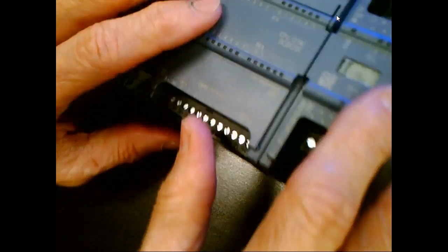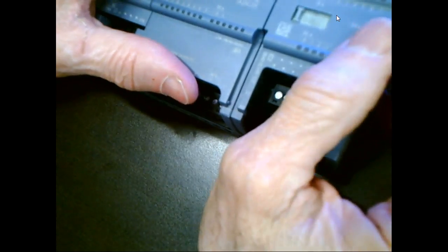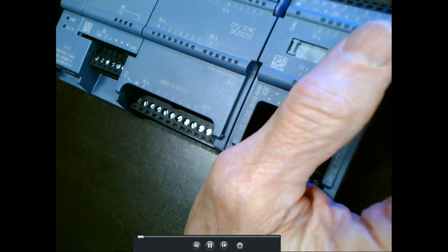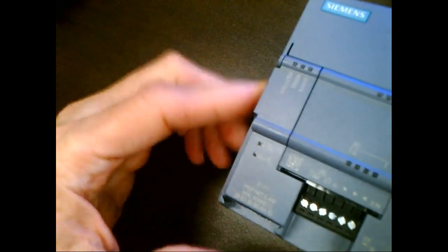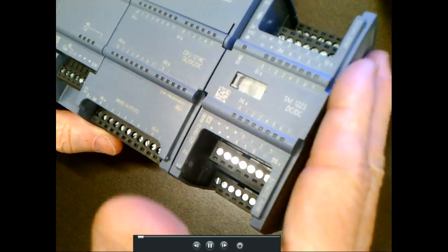And then we'll have to go into configuration and assign the module number for this guy. By default, it comes up and assigns it 8. And I think last time we just left it there, because it makes it real easy to differentiate going from 0 over to 8, right? So by default, this guy puts it on module 8. This guy's also got a second side on it. On the left-hand side, this is where your additional I/O modules go.